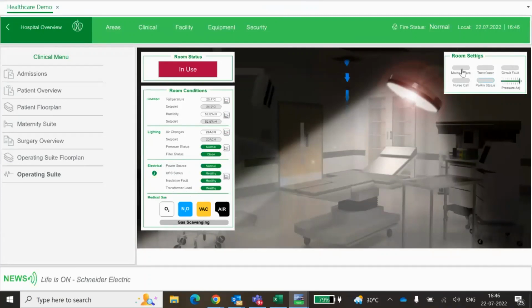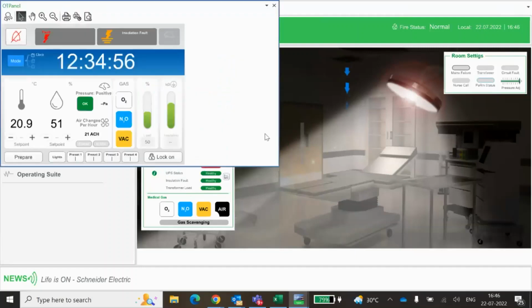During the operation, if there is a mains failure, the power source switches to the UPS, and the display reflects that the power has gone to UPS. The UPS may have a 20 minute backup, and if the operation needs to continue longer, the doctor decides whether to proceed or switch over to the DG.